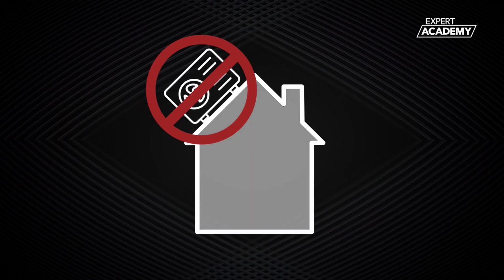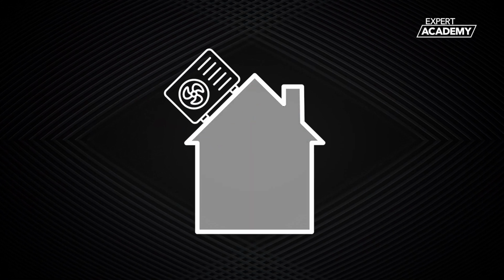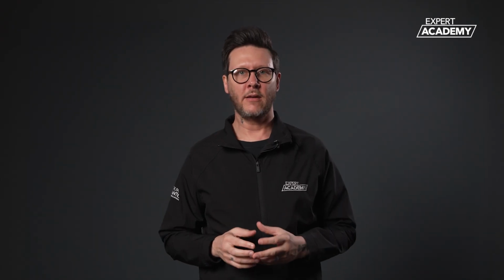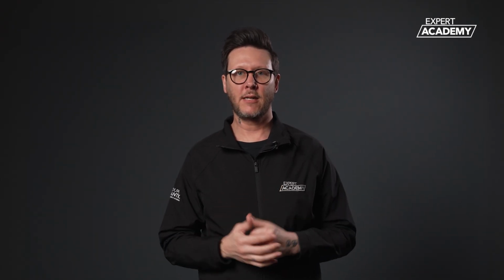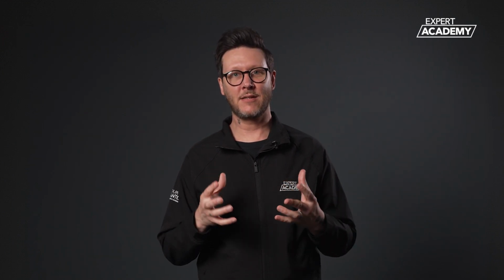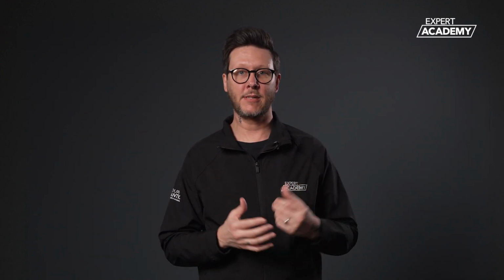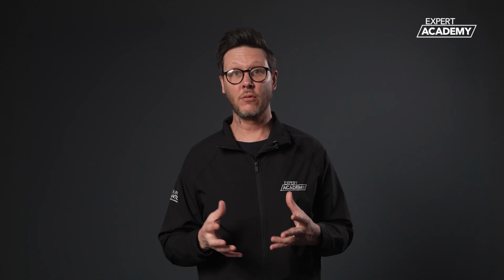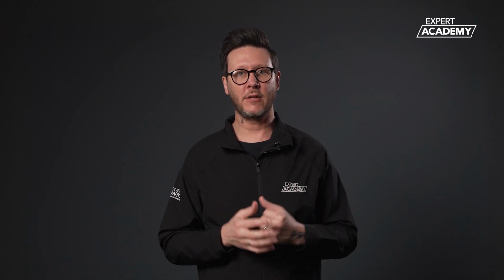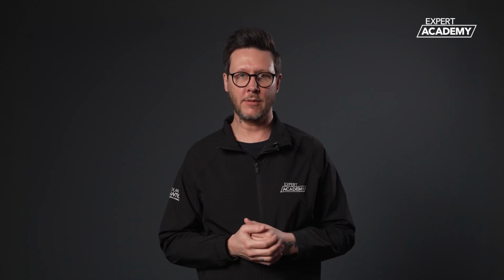Installations on pitched roofs will not qualify for permitted development. Installations on flat roofs can qualify, but the heat pump must be situated at least 1 metre from the external edge of the roof. It's important to mention here that the government has been in a consultation period since February 2024 with the goal of easing certain regulations regarding permitted development. For any rules relating to planning, please refer to the appropriate industry guidance documents.